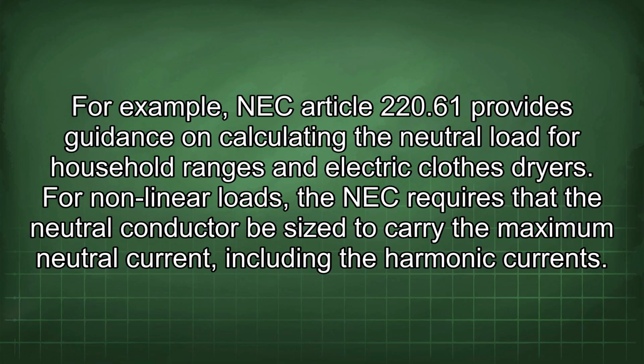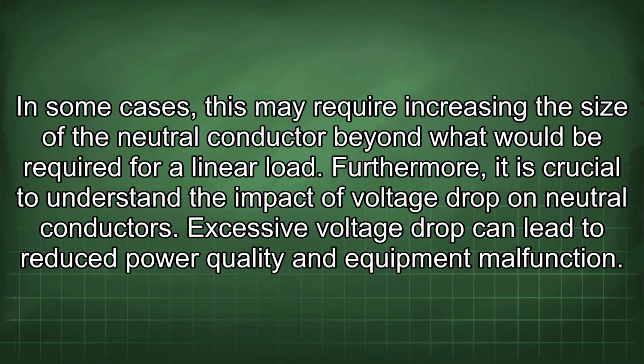For nonlinear loads, the NEC requires that the neutral conductor be sized to carry the maximum neutral current, including the harmonic currents. In some cases, this may require increasing the size of the neutral conductor beyond what would be required for a linear load. Furthermore, it is crucial to understand the impact of voltage drop on neutral conductors. Excessive voltage drop can lead to reduced power quality and equipment malfunction.